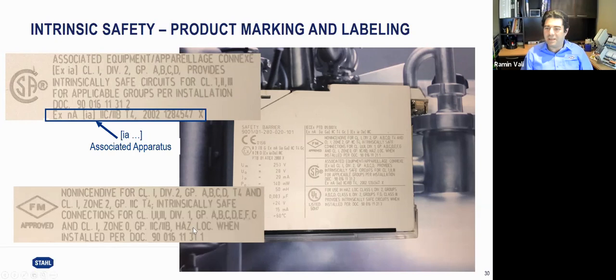When I zoom in on the FM certificate, again, that's one of the certificates we have. This is based on the division. It's more like a descriptive marking here. It mentions that it's an associated apparatus suitable for intrinsically safe connections in class 1, 2, 3, division 1, group ABC. So basically, it's more descriptive in the NEC 500 world compared to NEC 505.